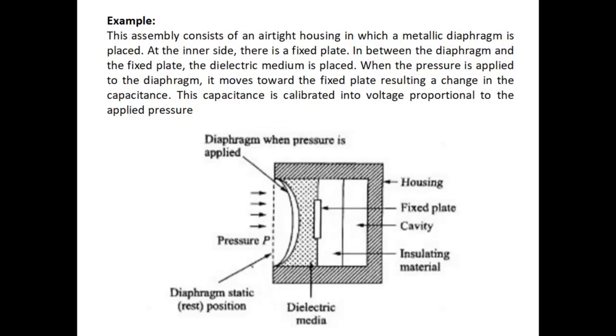For example, if I want to measure it using the capacitive fundamental, this assembly consists of an airtight housing in which a metallic diaphragm is placed. On the inner side there is a fixed plate, and between the diaphragm and the fixed plate a dielectric medium is placed.